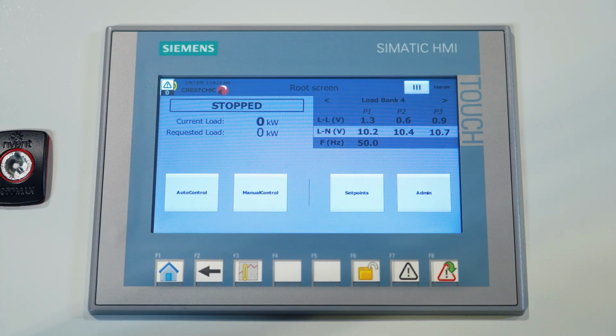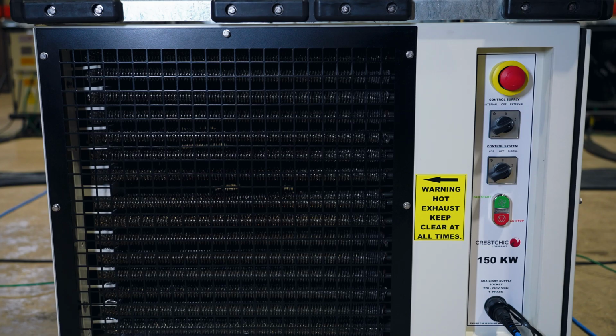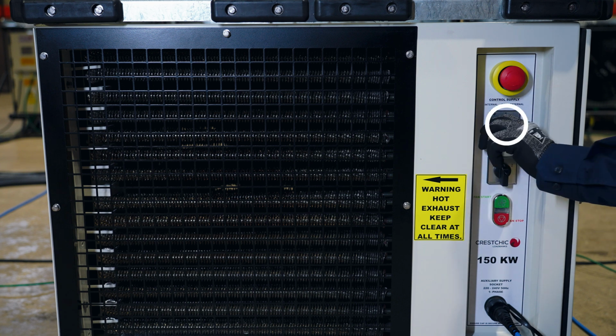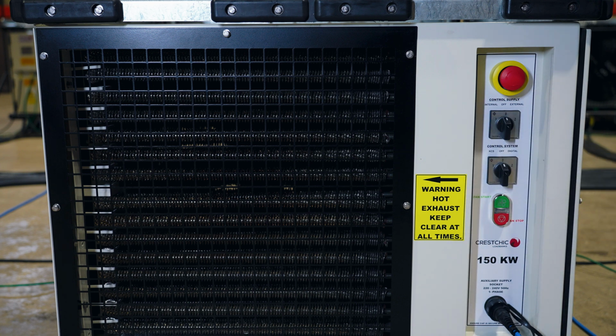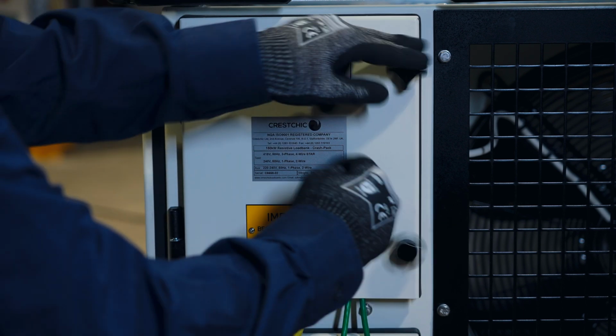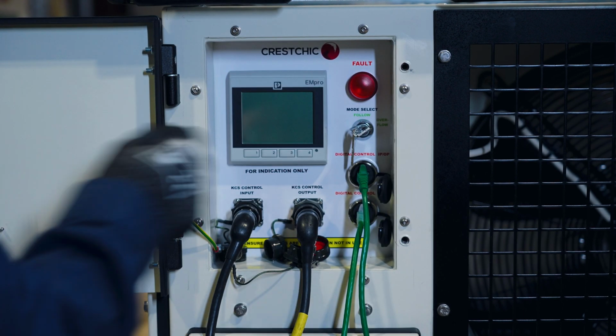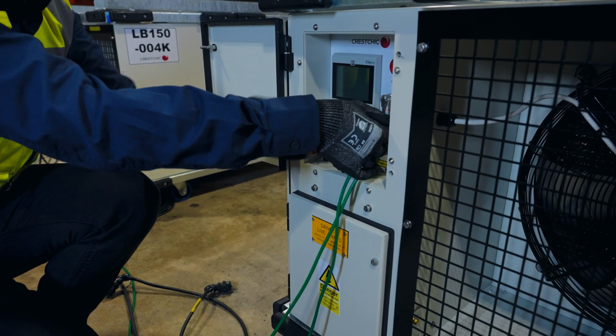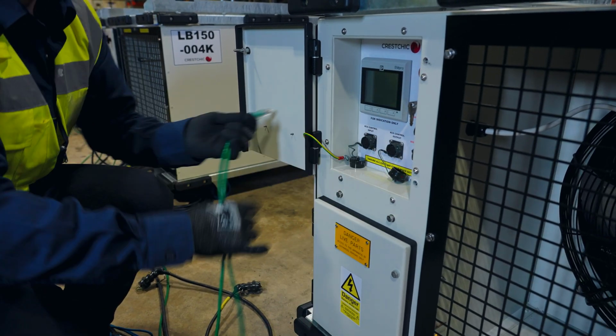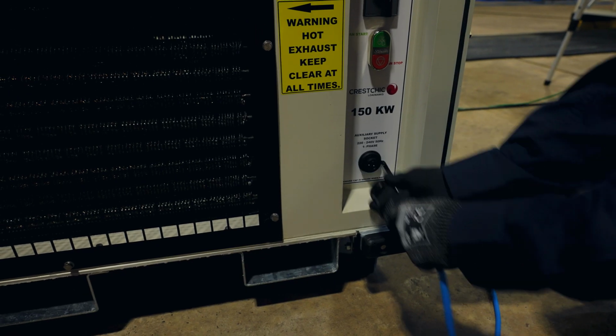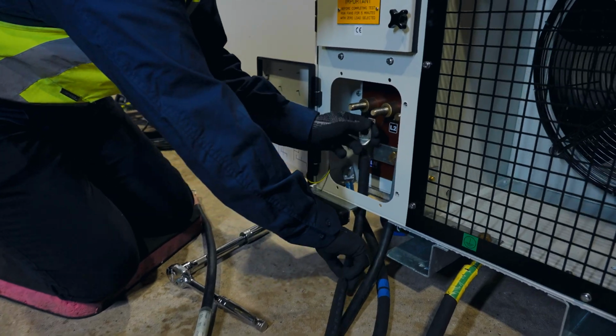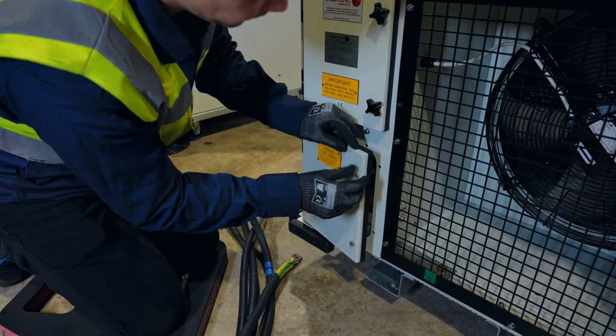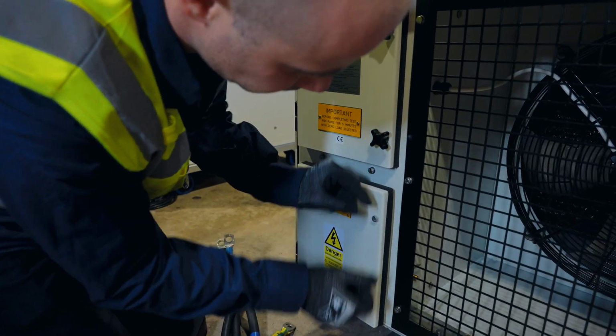Once the load test has been completed, the control supply switch can be switched to the off position and the supplies to the load bank can also be switched off. Once all testing has been completed and the load banks are to be removed, the controller and control cables should first be disconnected and put away safely. Then the auxiliary supply and load cables can be disconnected and removed. Finally, access doors to the load banks should be fully shut.